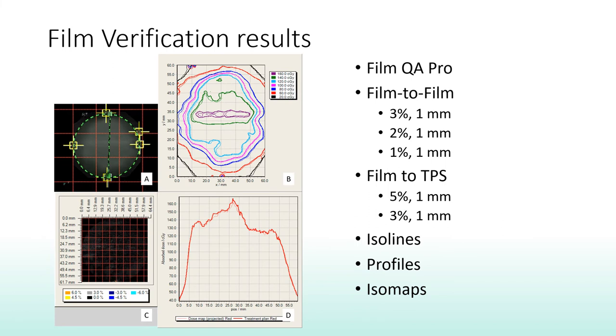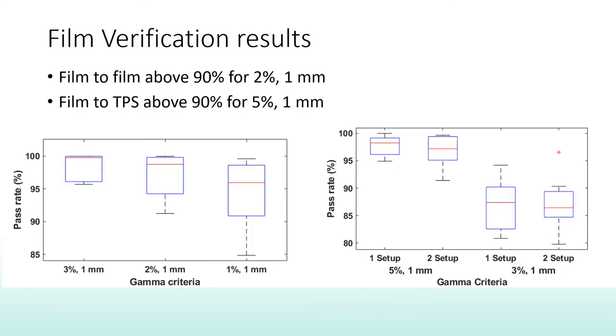Film analysis was done with FilmQA Pro. We used a 1 mm distance-to-agreement criteria, since that is our margin, and up to 5% for the TPS dose comparison. We also qualitatively evaluated the profiles, isomaps, and isodose plans. The film-to-film gamma analysis results are all above 90% for 2% and 1 mm, and film-to-TPS dose above 90% for 5% and 1 mm.